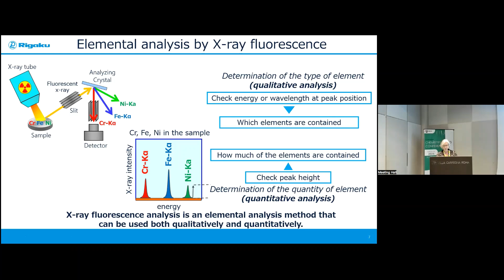Here we have an X-ray source which bombards our specimen with primary X-rays, and basically we get the fluorescent X-rays, which then go through a collimation system onto an analyzing crystal. This is why we call it a wavelength dispersive instrument, because this analyzing crystal has the function of separating our characteristic nickel, iron, and chrome K-alpha lines, which are then detected by our different detectors. Based on the intensity that we get, we will have a direct relationship with the concentration. As I mentioned, we can do qualitative or quantitative analysis.